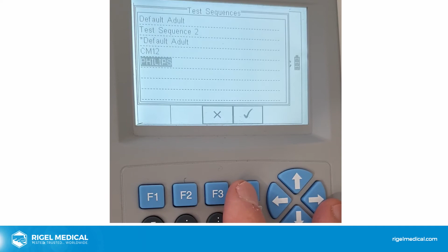So if I now go to automatic mode, no, sorry, one second. So with the Philips monitor or any patient monitor, we'll need to perform another zero. Go to the Pat menu, static IBP test, set to 0 manually, and then we'll zero the ABP on the monitor.